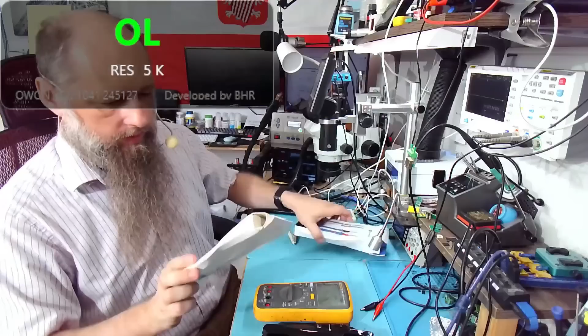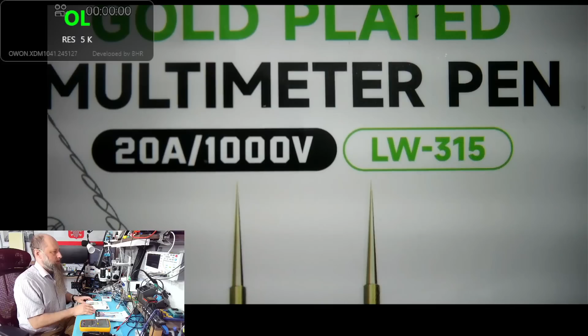And the final ones, the LW315, 20 amps, 1000 volts. That doesn't mean you can push 20 amps at 1000 volts through them - these are separate ratings. They can probably withstand 20 amps for a few seconds, at voltages around maybe 2, 5, or even 10 volts, and the insulation is rated for 1000 volts. And we have replaceable needles.